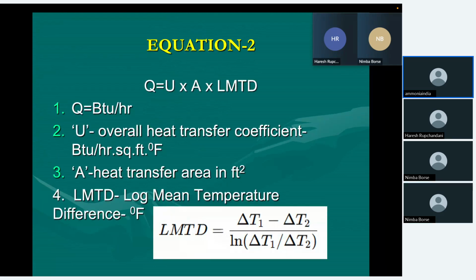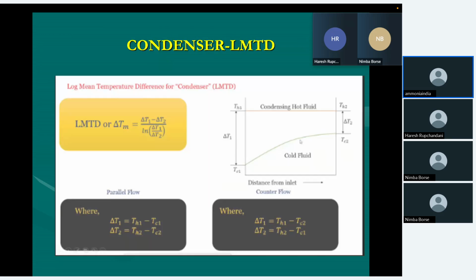Equation number 2 is Q equal to U A into LMTD. What is U? U is the overall heat transfer coefficient, BTU per hour per square feet per degree Fahrenheit. A is the area of heat transfer in square feet, and LMTD is the log mean temperature difference, that is, delta T1 minus delta T2 upon log to the base e of delta T1 upon delta T2. If you see in a condenser, what happens? The condensing temperature is constant, whereas your water temperature is increasing from 32 to 36 degrees centigrade. So delta T1 is condensing temperature minus inlet water temperature, and delta T2 is condensing temperature minus outlet temperature.